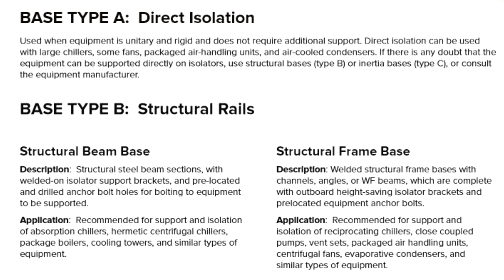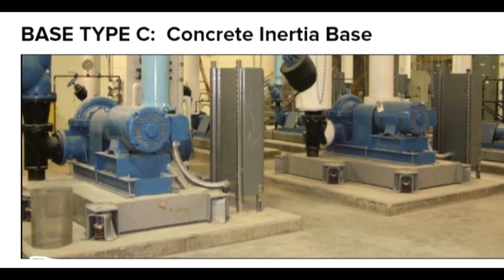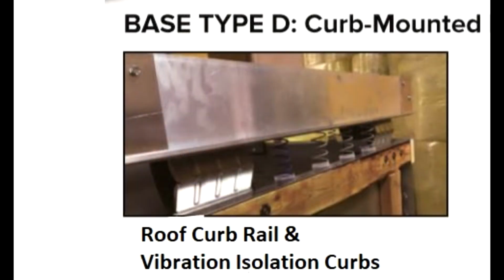Structural beam base: structural steel beam sections with welded on isolator support brackets and pre-located and drilled anchor bolt holes for bolting to the equipment to be supported. And structural frame base: welded structural frame base with channels, angles or WF beams, which are complete with outboard height saving isolator brackets and pre-located equipment anchor bolts. Here is some application. You can read. Base type C, concrete inertia base, and base type D, curb mounted base.